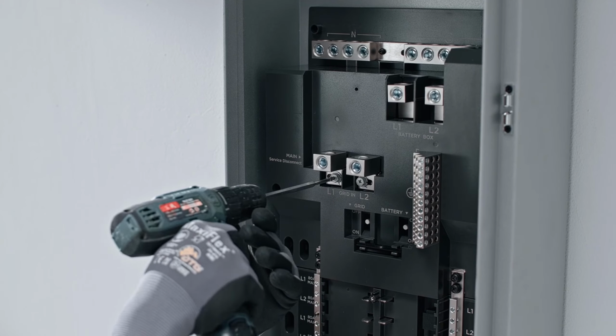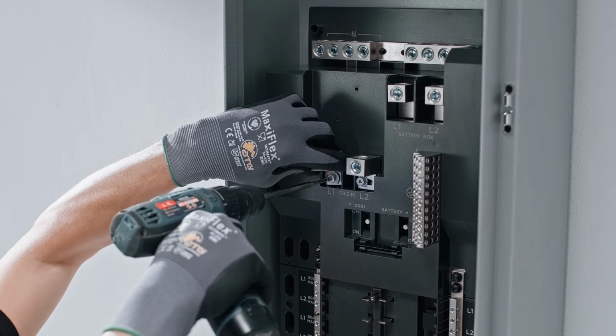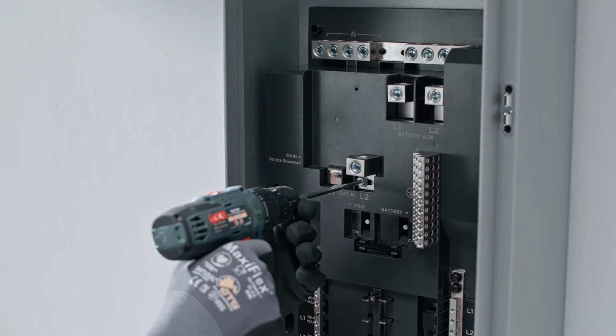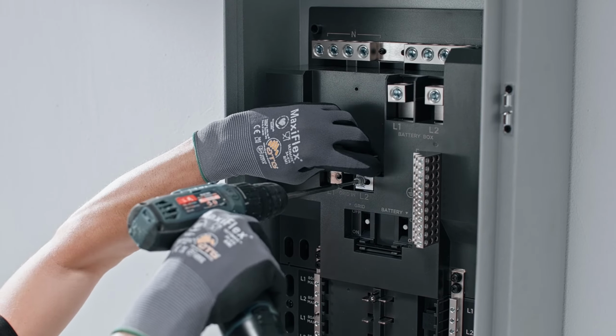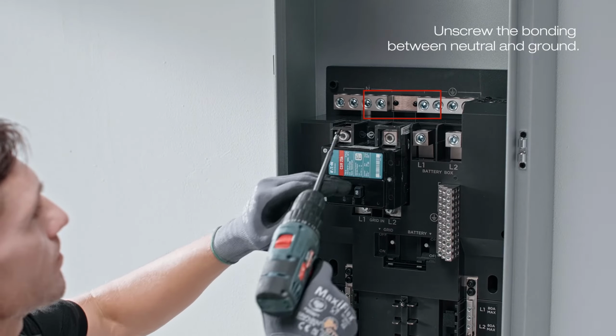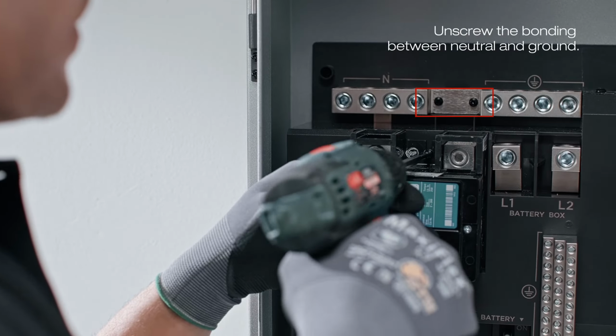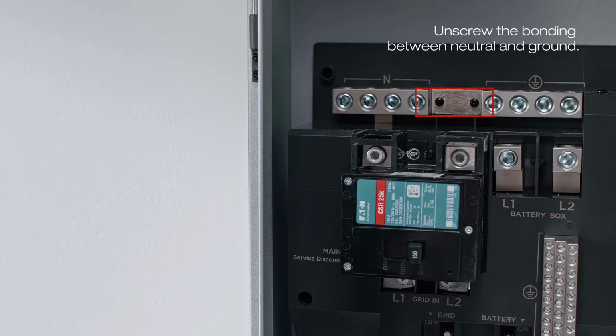Remove the main terminal before installing the circuit breaker. Install the main circuit breaker and secure it with screws. This panel is suitable for use as service entrance equipment. When used as a sub-panel, unscrew the bonding between neutral and ground.